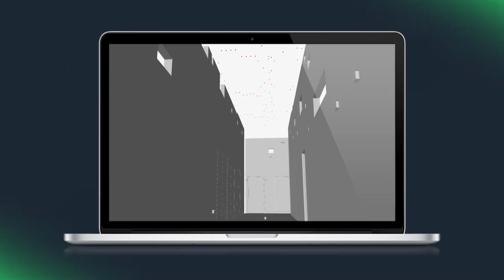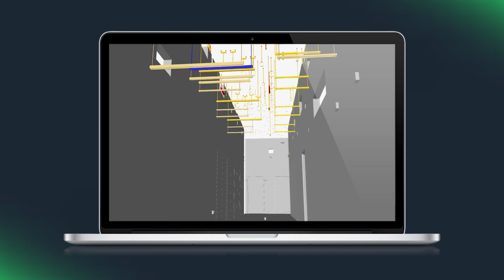The other thing I remember with the corridors was we ended up using Trimble field points, because we realised there were that many different sprinkler systems at the top, almost a blanket of sprinklers down the corridor with big main distribution pipes. We said once those pipes go up, no one's getting back to that slab again to drill it. So as the trades came lower and lower in that corridor, access back up to the slab just got more restricted. The idea then was using Trimble field points, pre-drilling the slab and getting all the anchors already installed with a rod, which was there for all the other trades to connect onto. That was a good solution for what could have been an absolute nightmare.